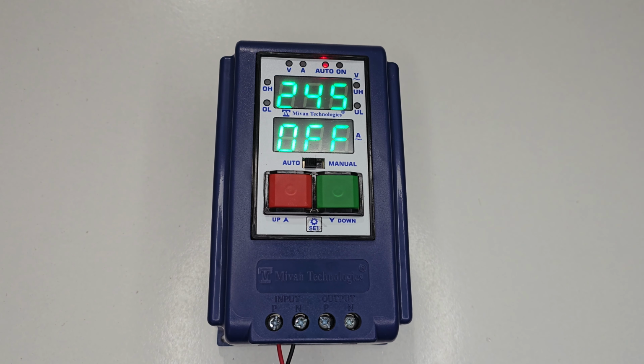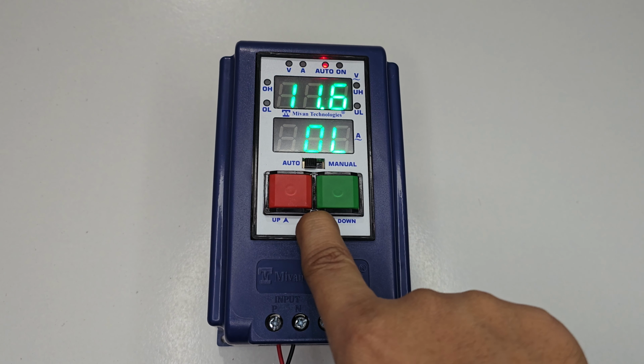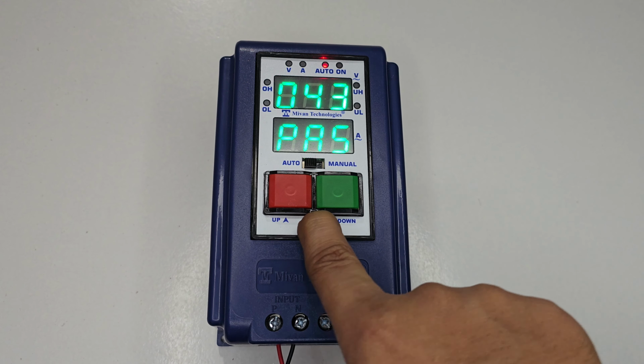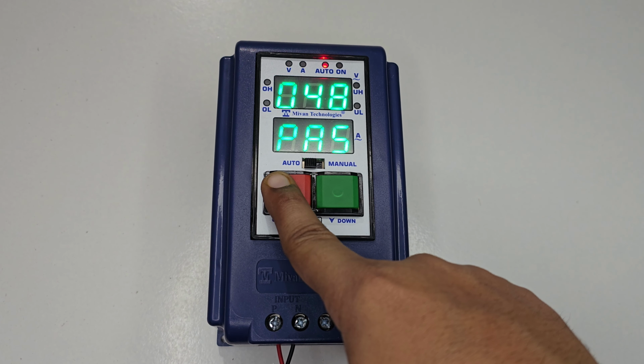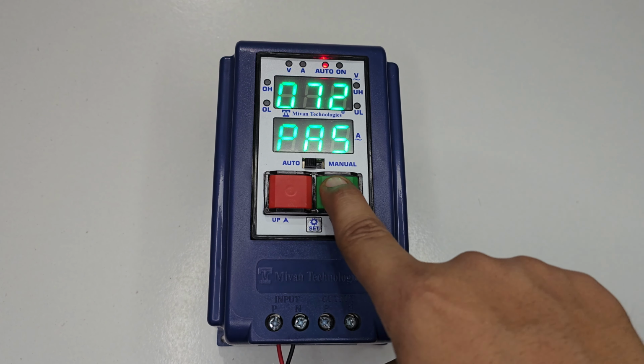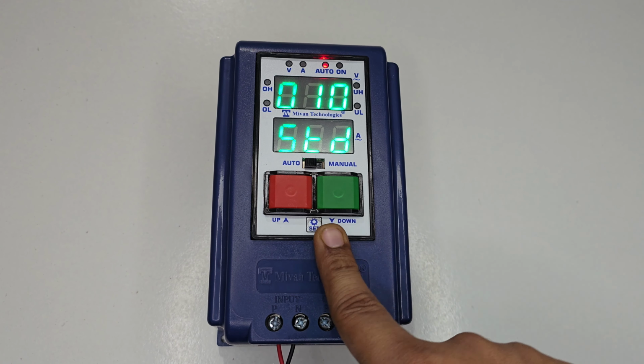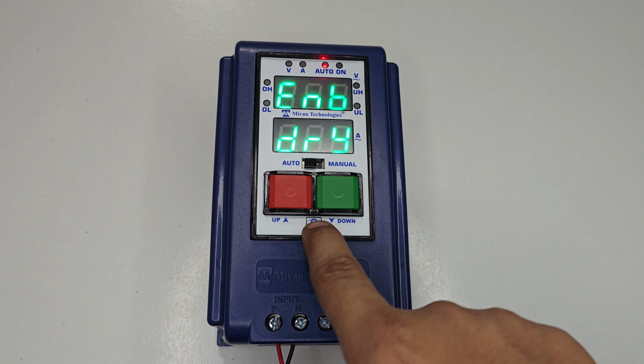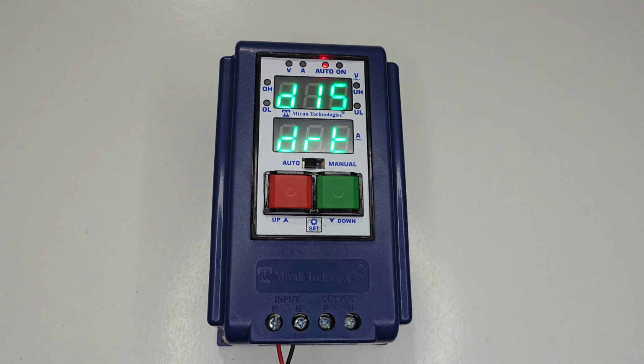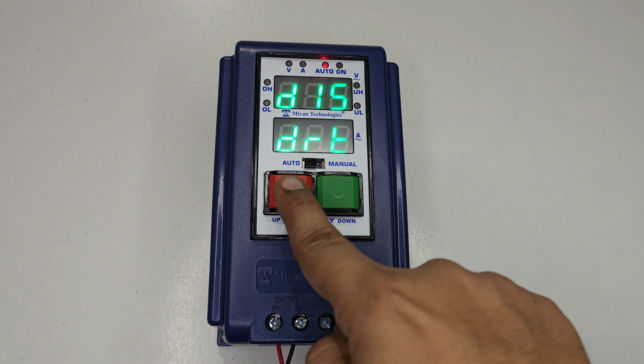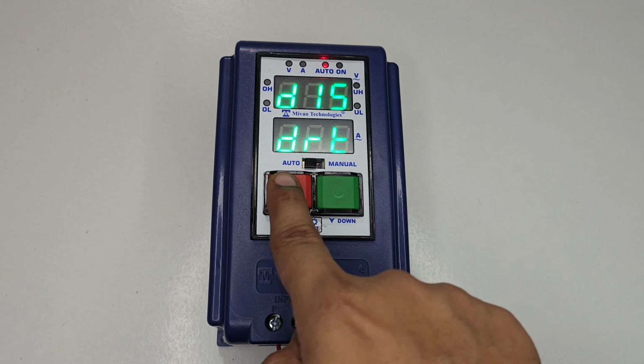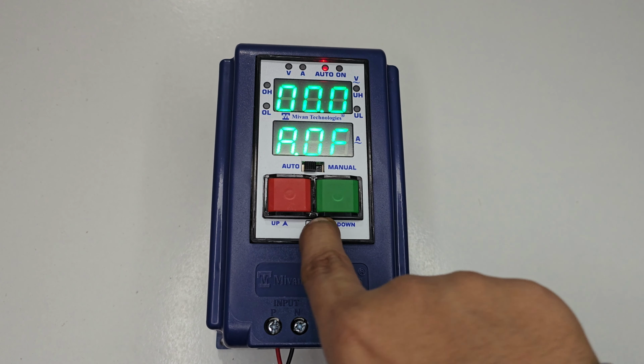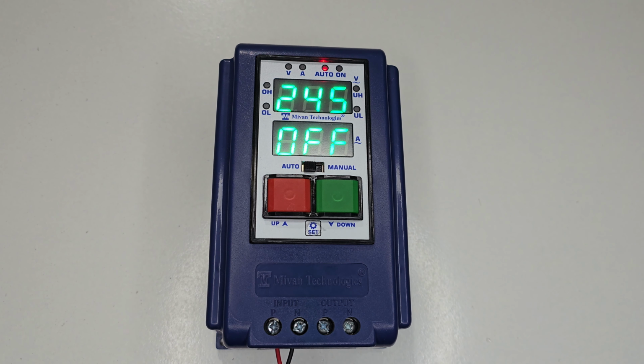Now I'll show you how to set the dry run reset timer. To set the dry run reset time, first you need to enable the dry run reset timer option from the password 70. Press the set button for 5 seconds. Go to password 70. Press the set button several times. Here you can see a dry run reset timer enable disable option. By pressing the up and down key, you can enable and disable. Make it enable, press the set button several times and it comes to the main menu.